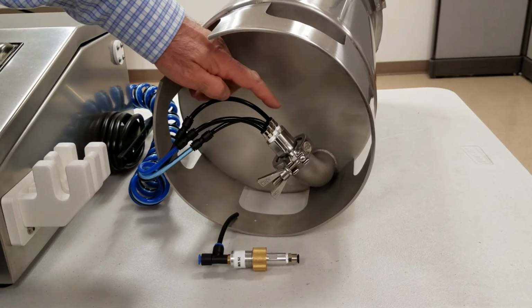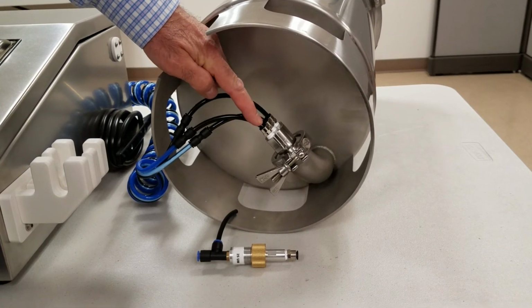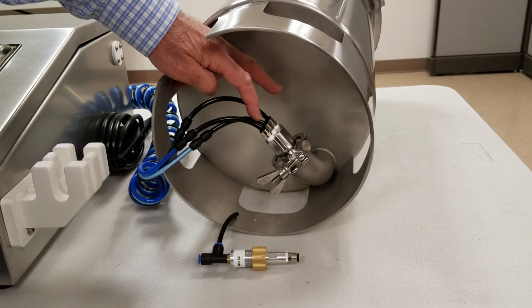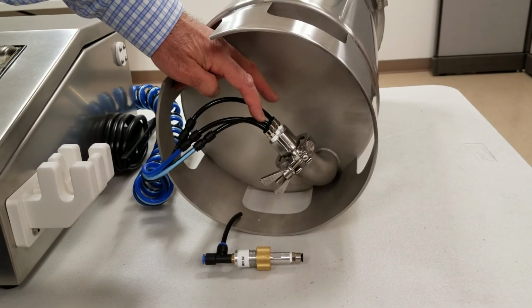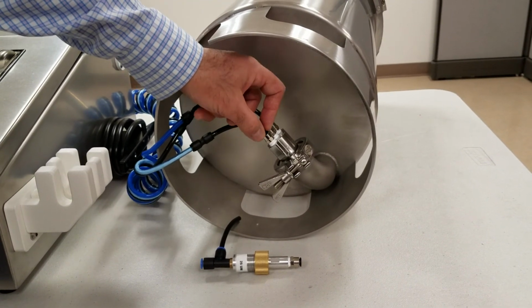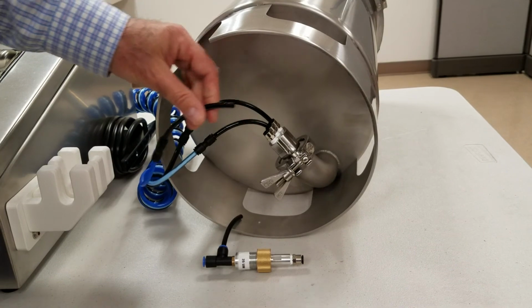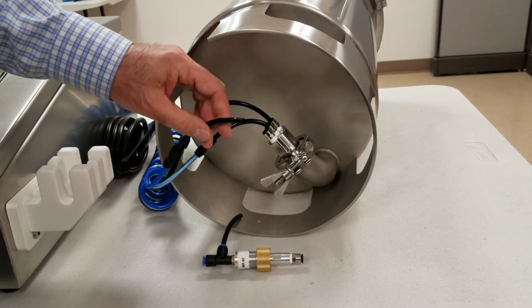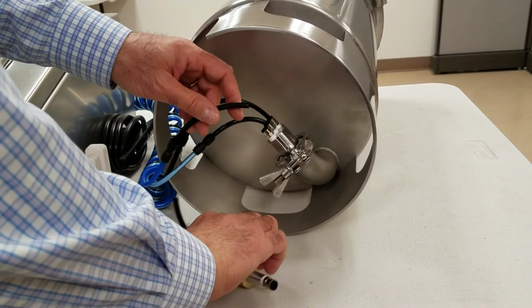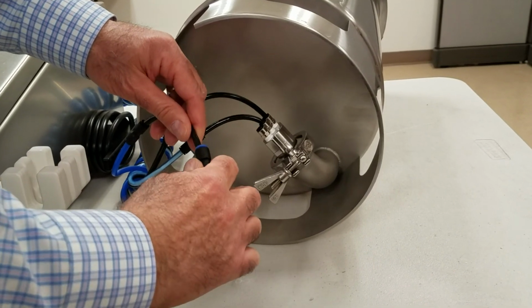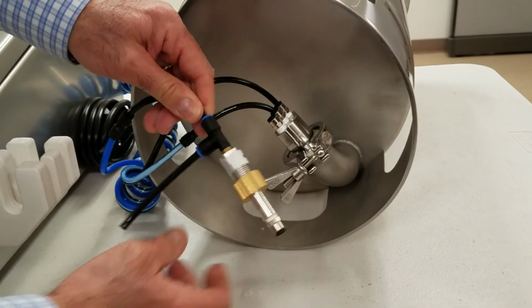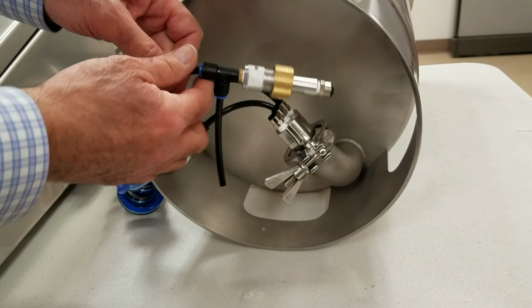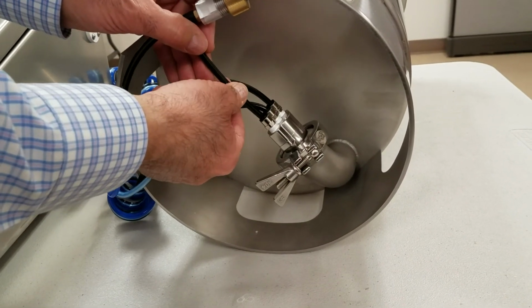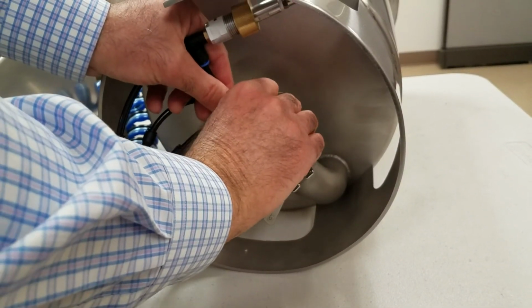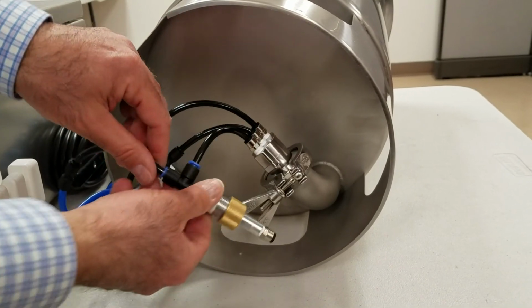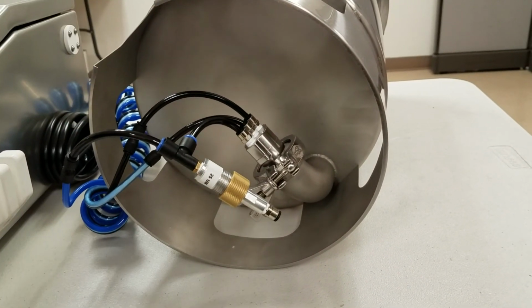You can see the probe assembly has 3 connections. 2 are pneumatic connections, and 1 is the RTD probe, temperature probe. So in order to install the adapter, I'm going to disconnect one of the pneumatic connections and connect that to the adapter, such as that, and then connect the other connection to, there you go, just like that.